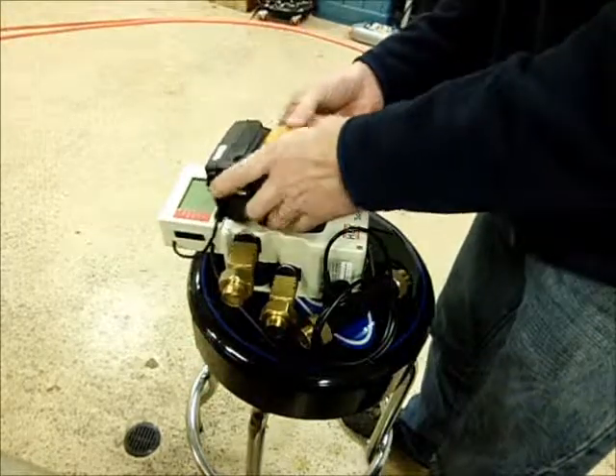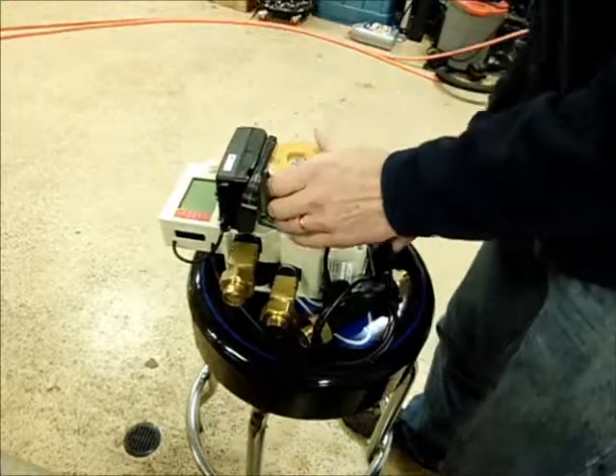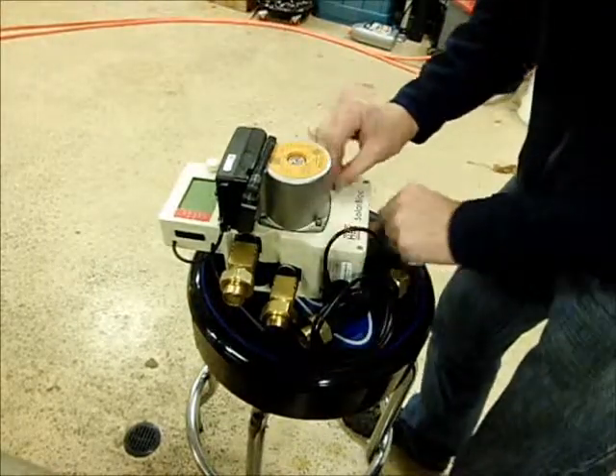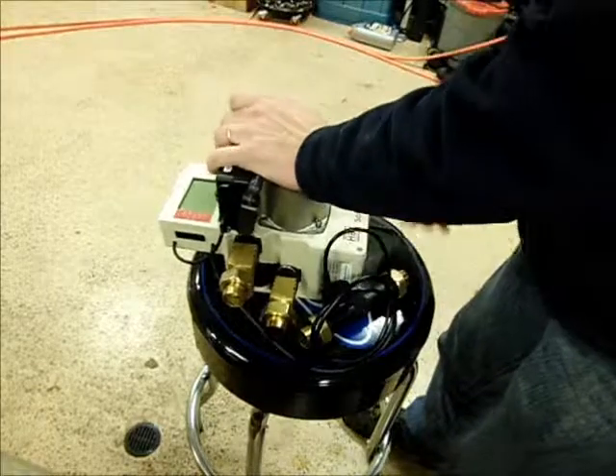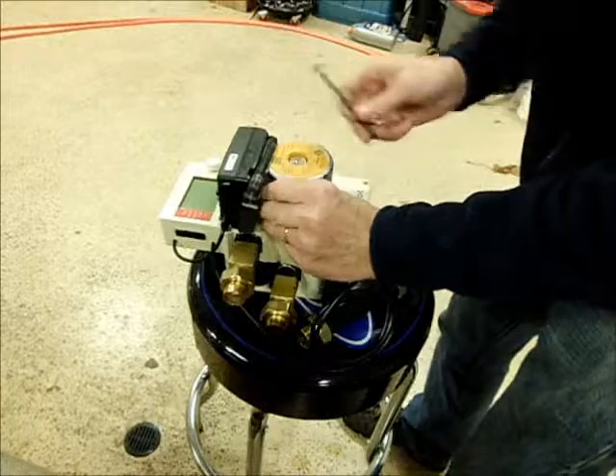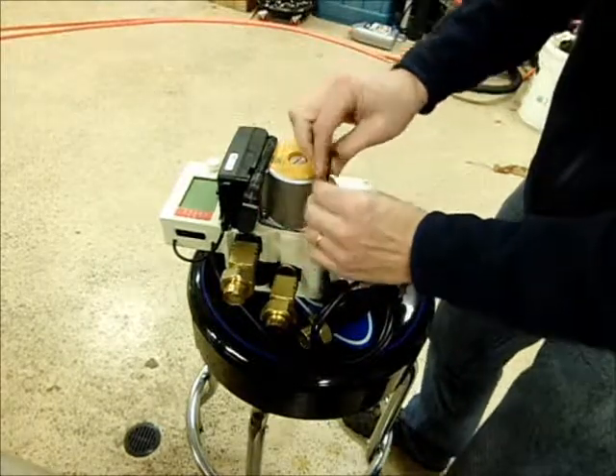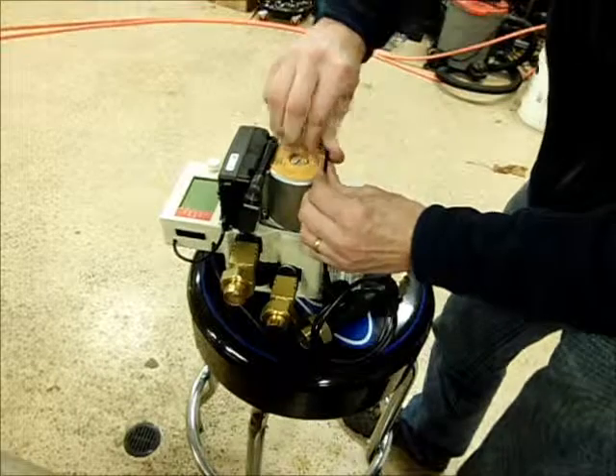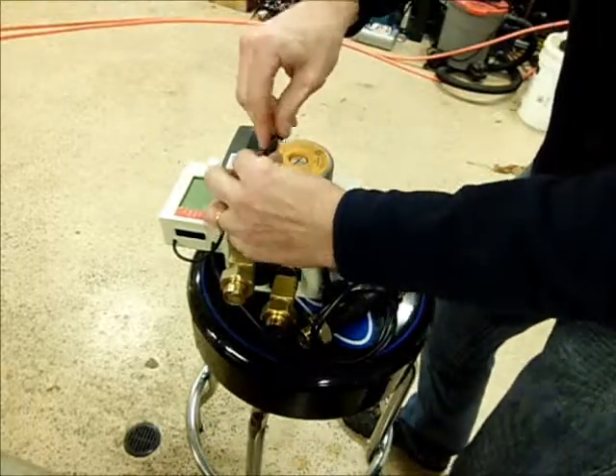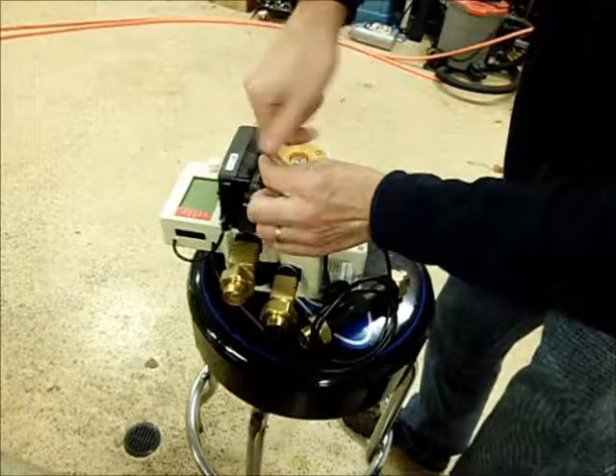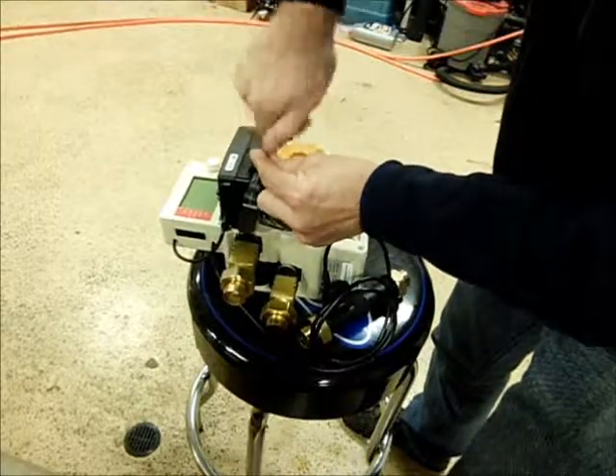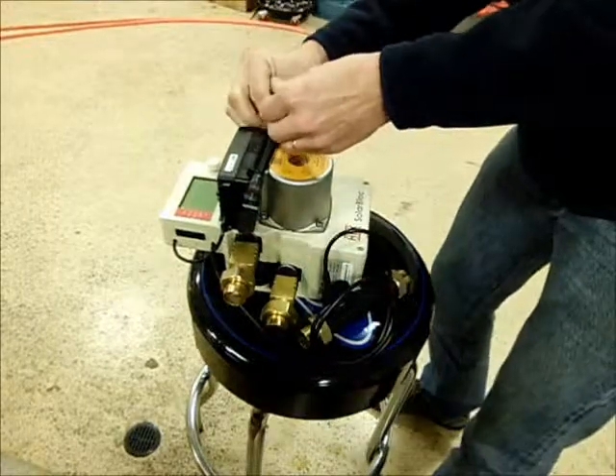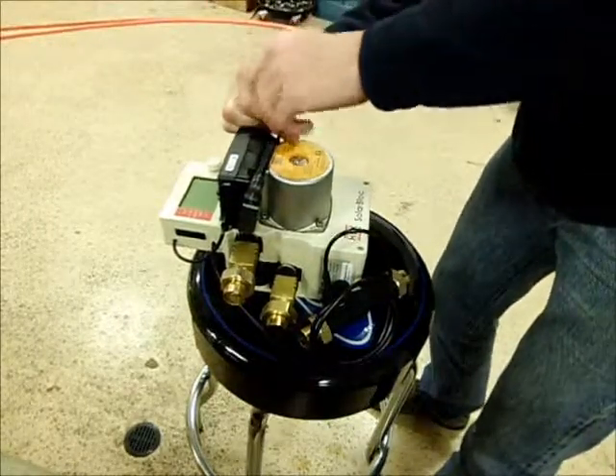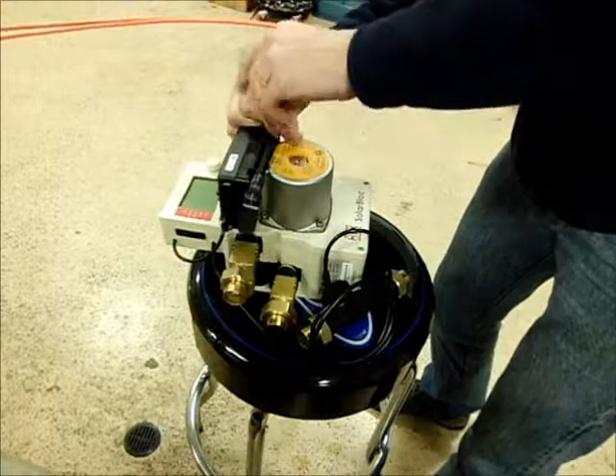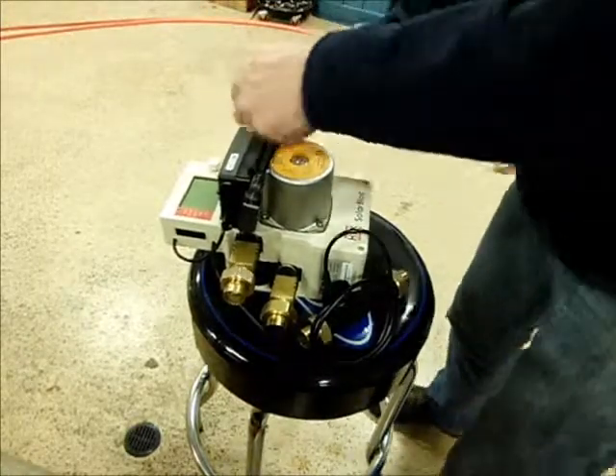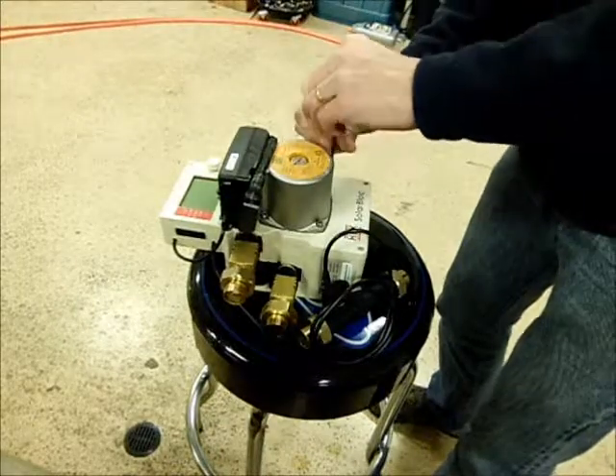Now I've got all the fittings in there. I'll just position this back on there, like so. Pop in your 4 Allen key bolts. This is a 4mm Allen key. And then you're good to go. Make all your copper connections. Mount the pump to the supplied bracket. And you can mount the pump through the actual bracket that this mounts on the wall with. Is not really a support for the pump, but it supports all the fittings, these brass fittings that fit in the pump. So I'll show you how that fits in just a second here.